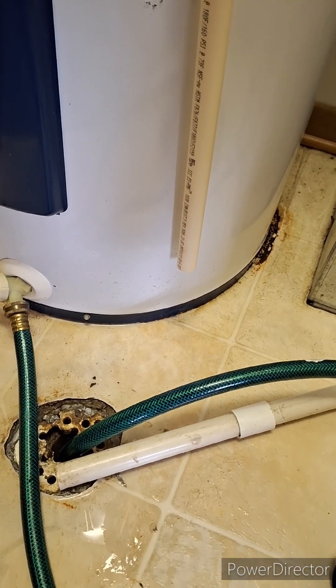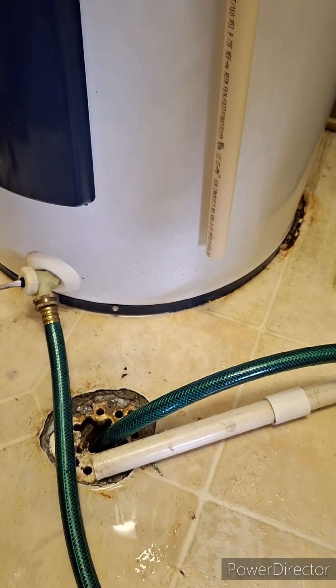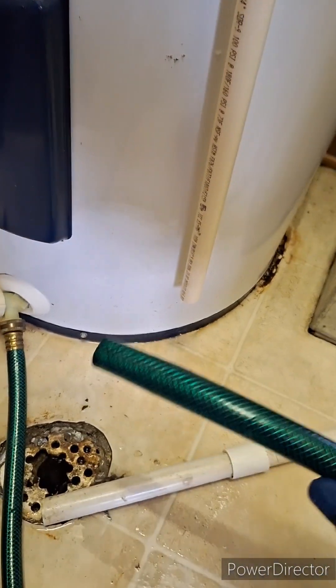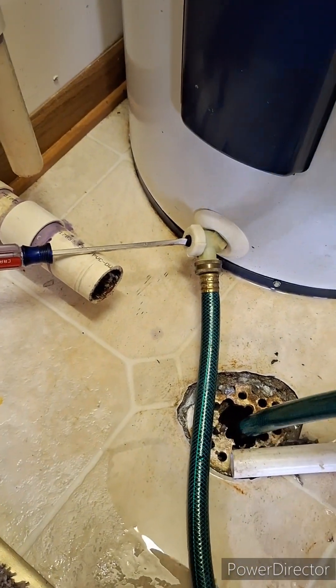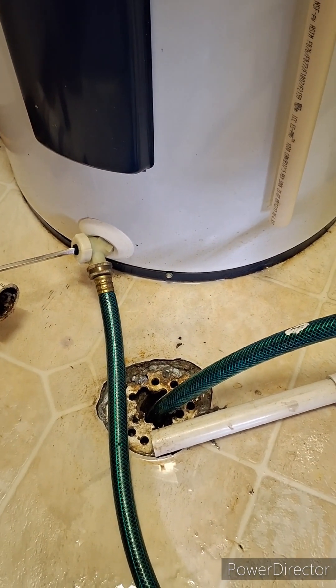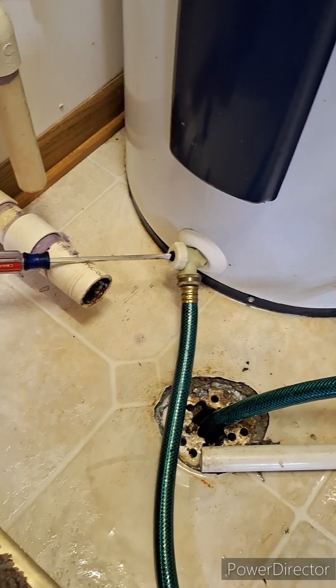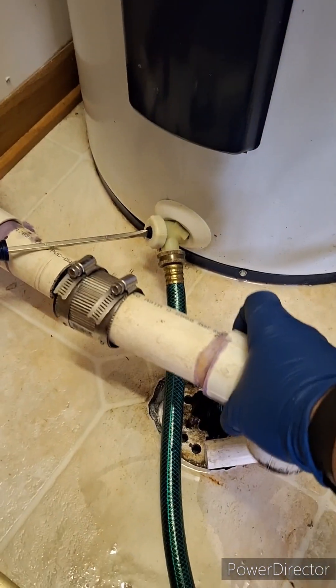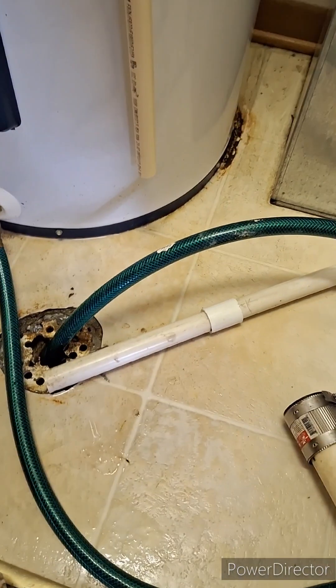If the water heater isn't leaking, I'll just have to determine that it's fine, and if there are future problems I'll come back and change it out. This pipe right here was full of sludge from the condensation, so I got a short hose, stuck it in there, and went up and down trying to clean the walls of the pipe and blow all that sludge down through the drain — hopefully that'll hold it off for a while. This pipe is the condensation drain for the two air conditioners above; it was added so that the condensation goes directly over the drain.